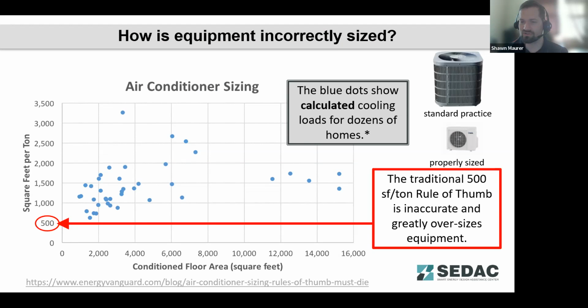Something we like to touch on again, making sure that your equipment is properly sized to buildings, avoiding rule of thumb calculations. This is just a residential example where the typical rule of thumb is about 500, 600 square foot per ton. And we're finding now with even code minimum buildings that that's closer to 1,200 to 1,500 square foot per ton. And some high performance buildings are much better than that. Same thing with commercial buildings. If you're getting a rule of thumb calculation, again, we see that 500 square foot per ton applied to commercial buildings as well. You kind of know that they haven't done proper work for the sizing of that system. You might want to have them go back and do a proper sizing calculation or a building model, whatever method they're using to determine the equipment sizing.